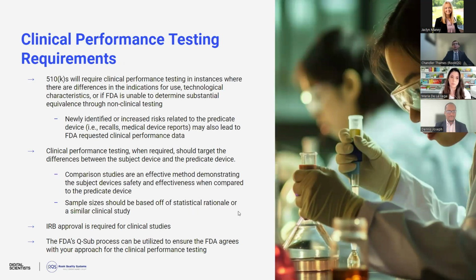So for clinical performance testing requirements, this is going to vary more than performance testing requirements based off of your regulatory pathway. So for 510(k)s, typically clinical performance testing isn't required. However, when we were discussing predicate devices and substantial equivalence, we touched on needing to make sure that the indications for use and the technology used is similar enough to claim substantial equivalence. Any differences in those need to be assessed to determine if you can bridge that gap with non-clinical performance testing. If that's not possible, then you would need to implement some clinical performance testing. So while it's not necessarily required, it may be. Just because you're a 510(k) doesn't mean you don't have to provide clinical data, but it's just less common.